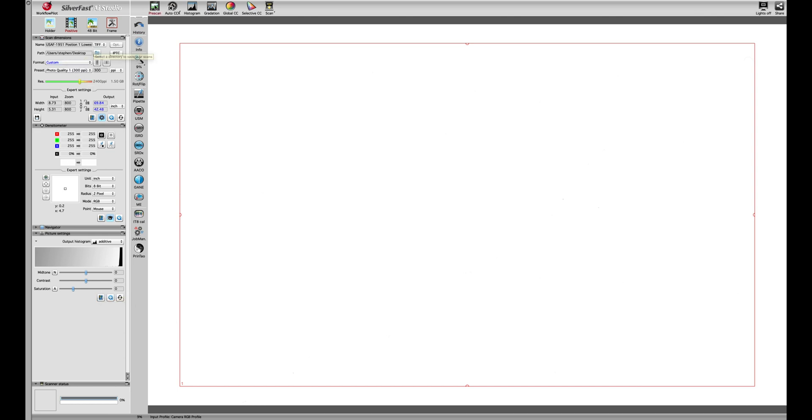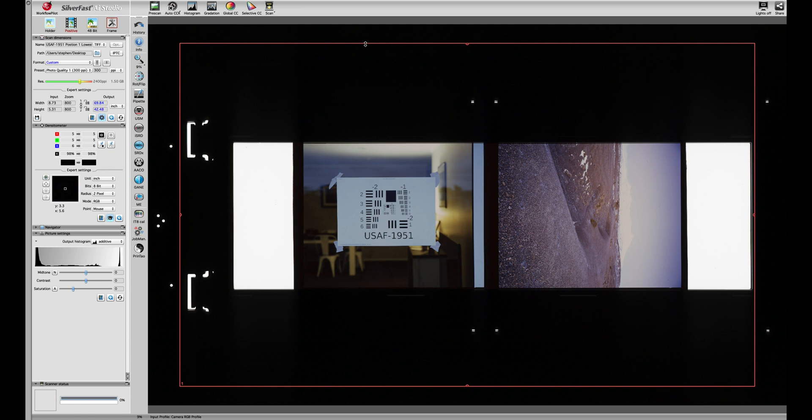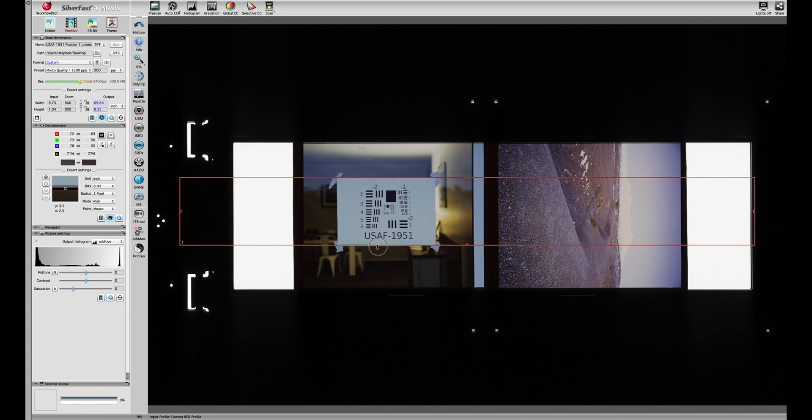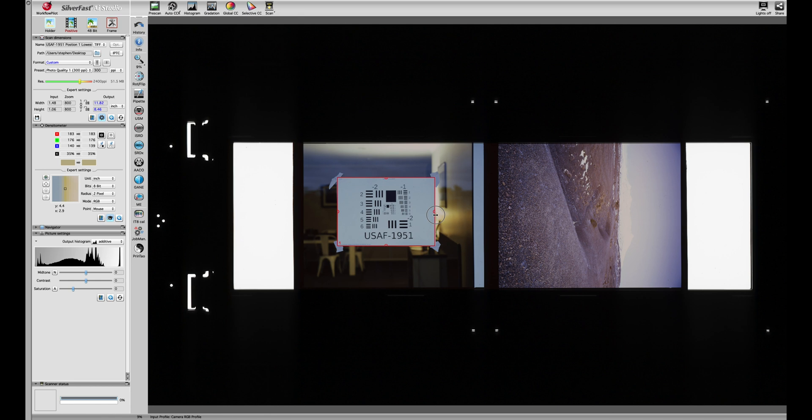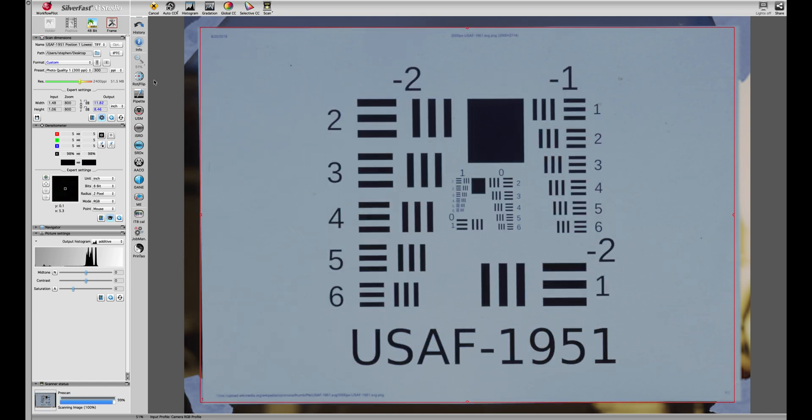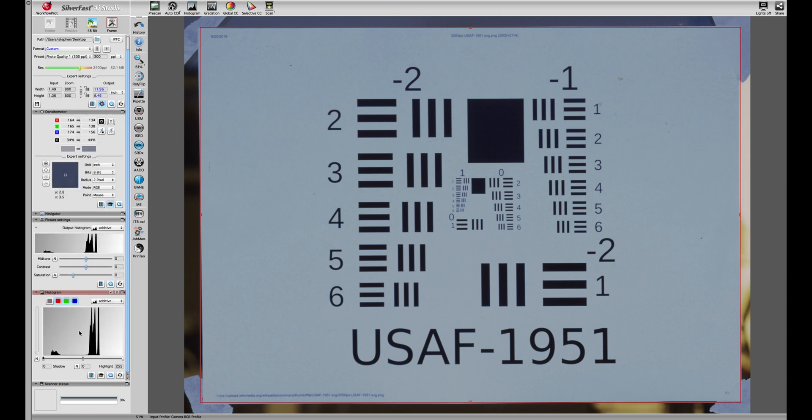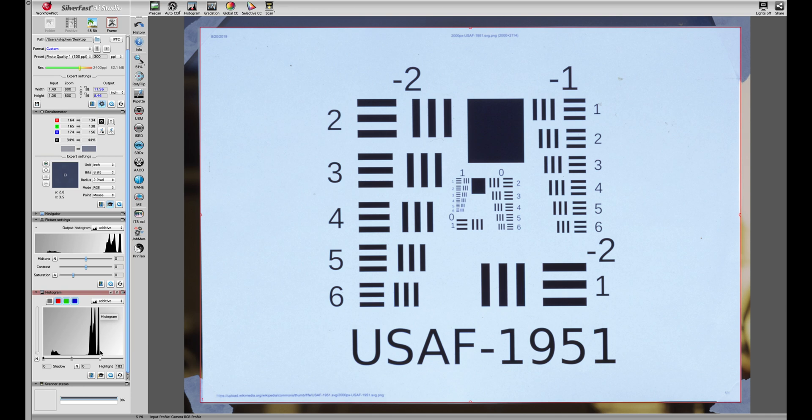Now I'm going to do a pre-scan. Once the pre-scan is finished we just align the scan area with the USAF chart, then zoom in for a more detailed scan. We'll adjust the borders a little bit. Now we're going to add a histogram and bring the white point down to brighten up the image, aligning it with the end of the white on the histogram scale. Then we're going to go ahead and scan.